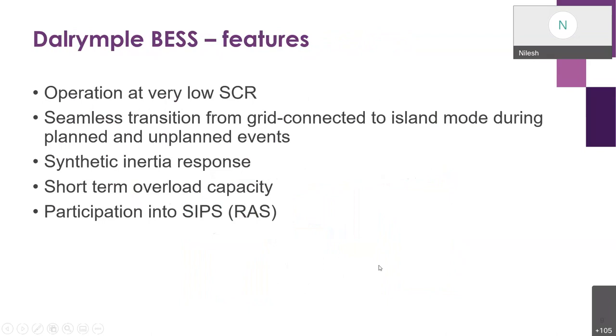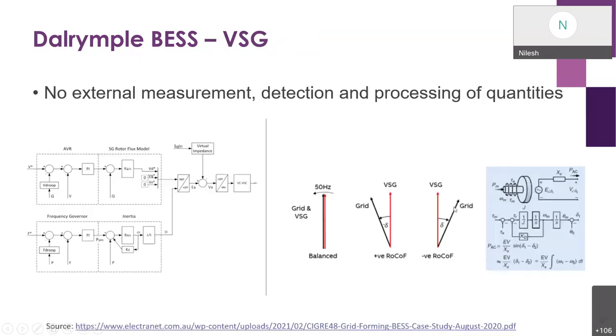Some of the features of these batteries: it has shown that it can stably operate at very low short circuit levels. It has demonstrated a seamless transition from grid connected to island mode during a planned and an unplanned event. It also provides a synthetic inertia response. In the next few slides, I'll show you how it responds. It has a short-term overload capacity as well to support the protection system around that part of the network. It's a very small microgrid. It also participates in the system integrity protection scheme, or remedial action scheme, as it is often known.